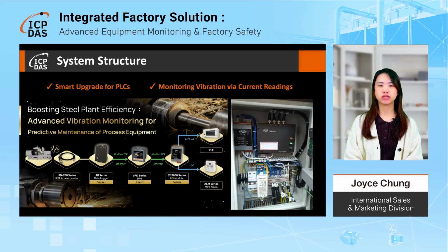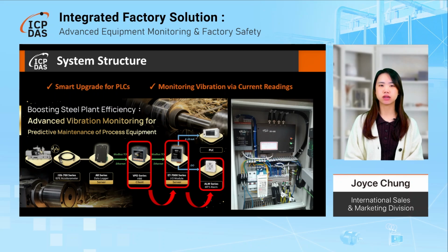ICP-DAS equipment vibration monitoring and predictive maintenance solution utilizes the AR series accelerometer data logger to record and recalculate the machine vibration values and set vibration threshold levels. The VPD series HMI retrieves the data via the Modbus TCP communication protocol for real-time display. The data is then transmitted through the ET7000 series I/O module via Modbus TCP and subsequently forwarded to the PLC. This is the smart upgrade for traditional PLCs, enabling PLC users to monitor equipment vibration through current readings. Additionally, if the VPD series HMI detects abnormal vibrations, it triggers the ALM series sound alert module via the ET7000 series I/O module.